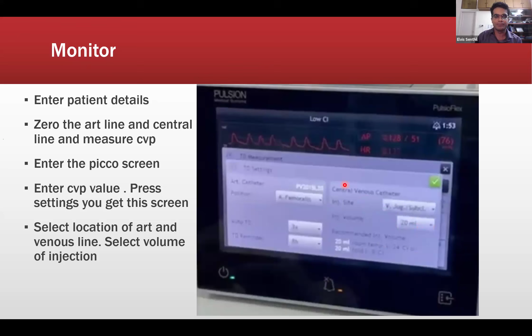Here's a short video showing how you start. It tells you to inject 20 ml, and then you want to inject it slowly and gently through the distal port of the central line, through that injection cannula with the blue temperature probe. Once the machine detects that you have injected it, you will get a next screen. Now, one thing you want to do is inject 2 or 3 times to get a good value of the cardiac output.